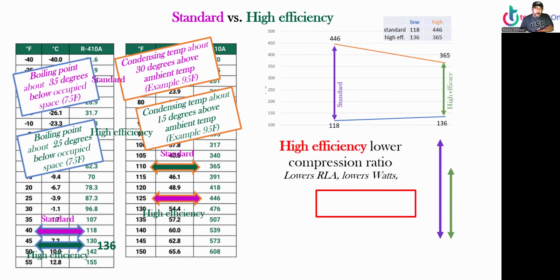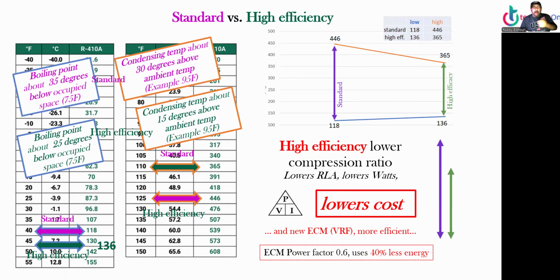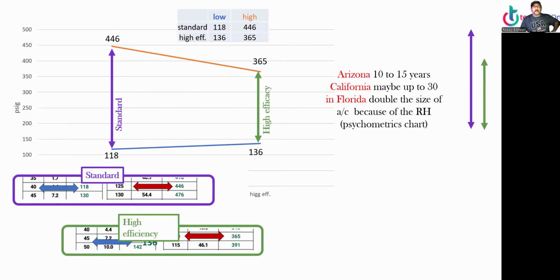Higher efficiency, lower compression ratio, lower rated load amps, lower watts, and using Watt's law, lower cost. And now with the new technology, ECM, electronically commutated motors, and variable refrigerant flow, even more efficient. ECM with a power factor of 0.6 uses 40% less energy. So with the new ECM and the new high efficiency condenser and high efficiency evaporator, we are lowering costs a lot. And that's why we replace those things.